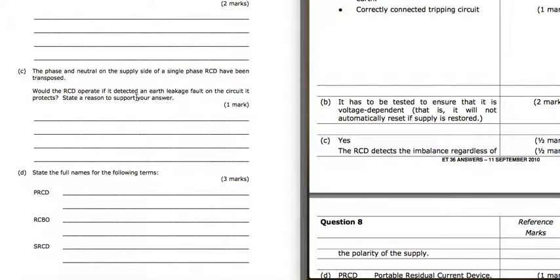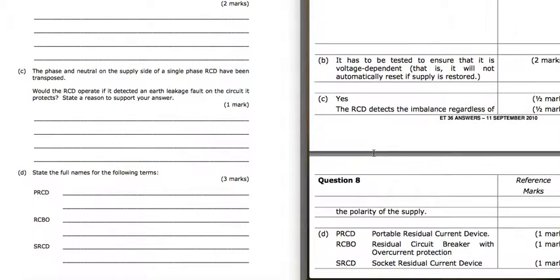Phase and neutral have been transposed. Is that going to affect the RCD operation? It's not going to affect it. So would it still operate? Yes, because it's looking for an imbalance regardless of the polarity of the supply. It doesn't care if phase goes in first or neutral. It's just if they're both the same currents, then it won't trip.